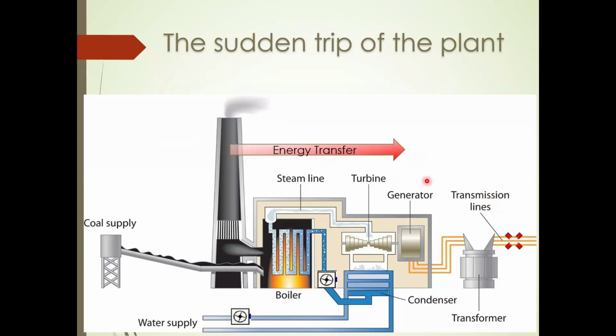Now, what happens if you trip the plant for some reason, automatically or otherwise, is that the energy generated here will get stuck here. In order to avoid the turbine going overspeed, you have to close the governor valves here. Also, inside the turbine and many other equipment, you have some residual steam left. So that steam will be directly dumped to the condenser.